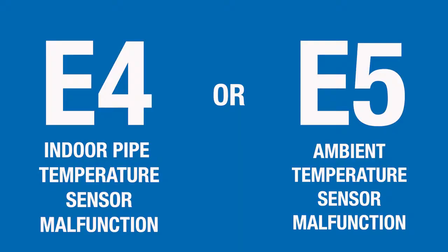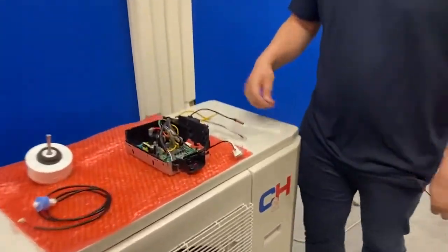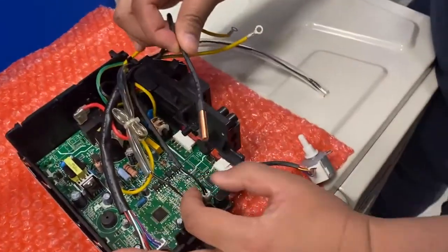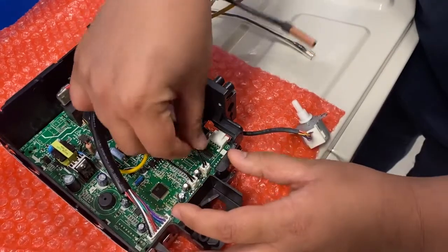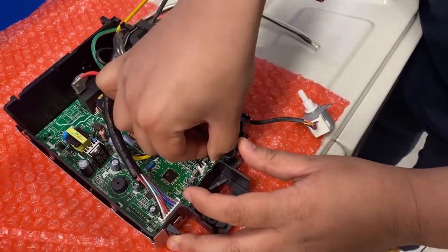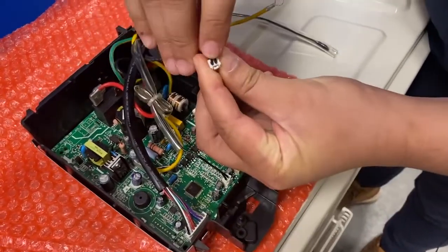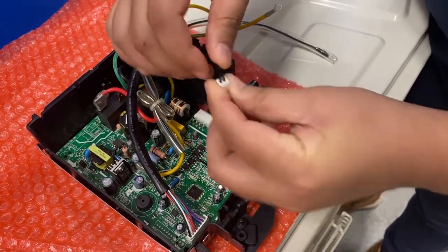If your indoor unit is displaying an E4 or E5 error code, that indicates an indoor pipe temperature sensor or room temperature sensor malfunction. To troubleshoot, first I will locate the pipe temperature sensor, which looks like this. I would make sure it's properly connected. Then I will check resistance between the 2 pins.